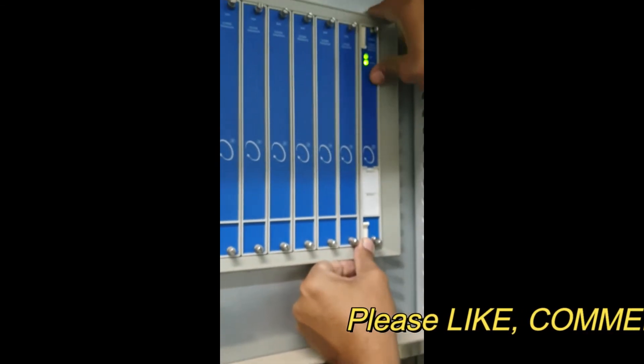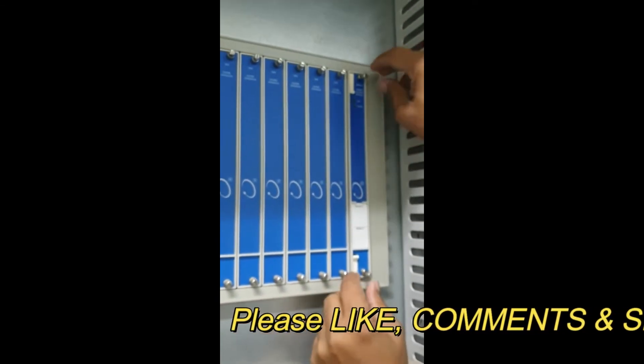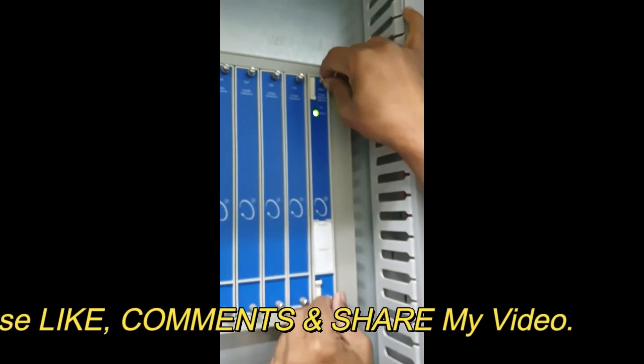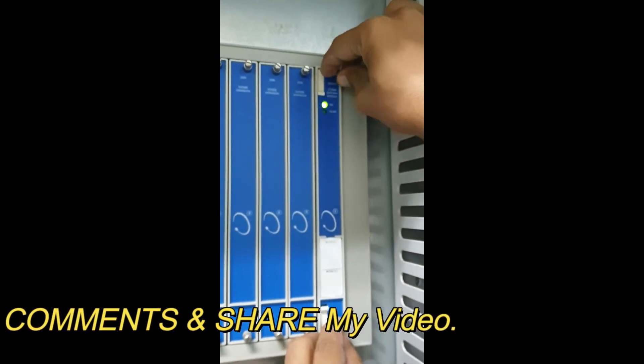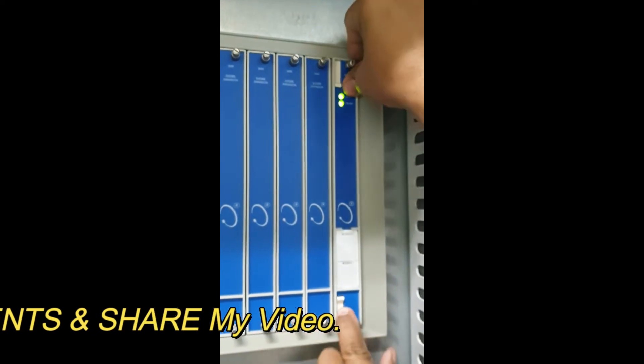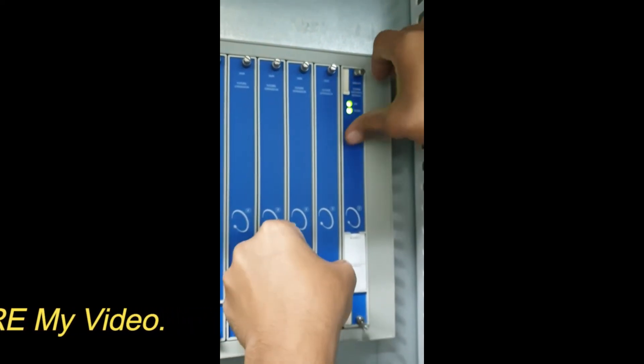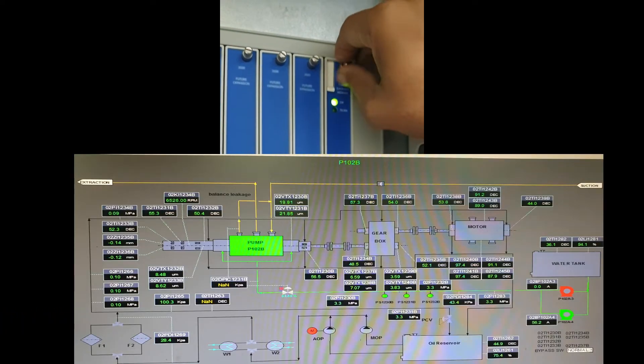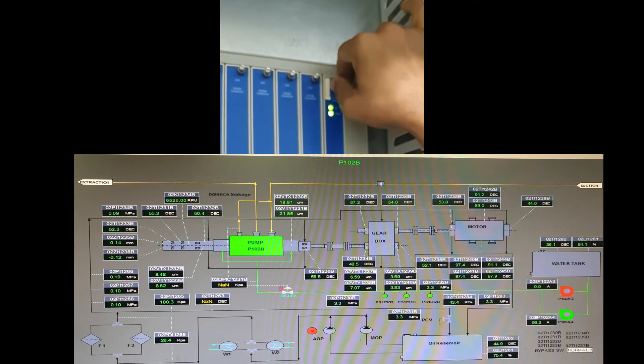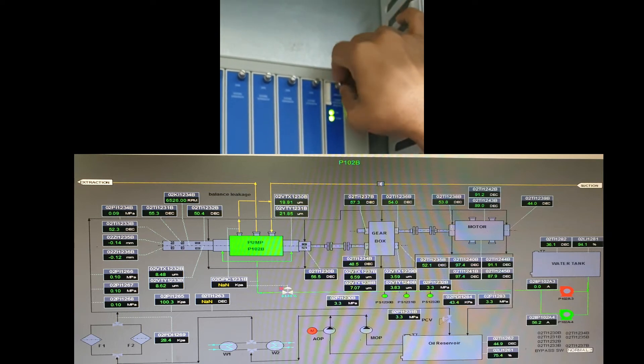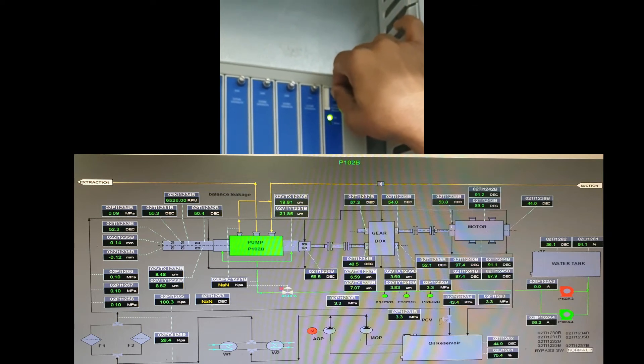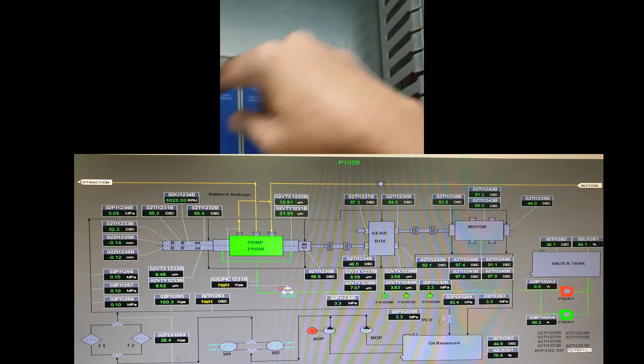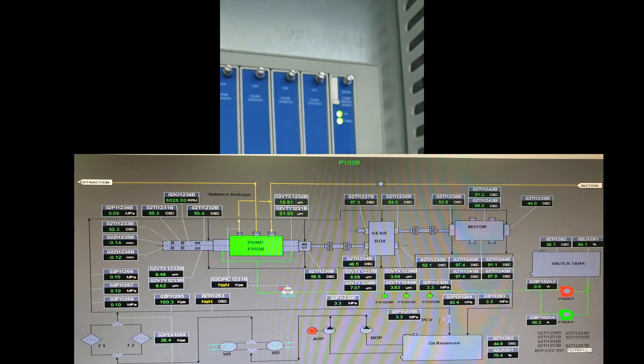I press the card in and you can see that it is getting power from the rack system and becoming ok status. The card already has power and the LEDs are blinking — the ok status LED and the transmitting LED are both blinking. When configuration is complete, the ok LED will be steady and the transmitting LED will be transmitting. Now you can see that the ok LED is steady and the transmitting and receiving LEDs are blinking. Previously the LEDs were not blinking, meaning it was not communicating, but now the ok LED is steady and the transmitting LED is blinking.